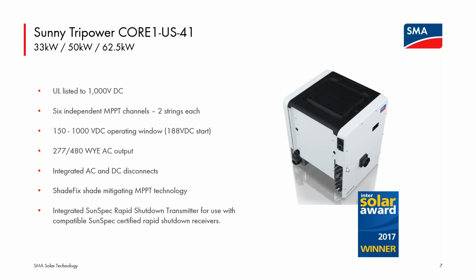The DC inputs, we'll talk about these connectors. These are Amphenol UTX connectors here at the bulkhead of the inverter. We include in the accessories bag shipped with each and every inverter the mating Amphenol UTX connectors and ferrules to crimp on the inverter end of the home run cables coming from the array. So installers will be able to mate Amphenol UTX to Amphenol UTX at the inverter bulkhead. And we provide sealing caps for any unused inputs. You can load the inverter unequally. You don't have to use all of the inputs, but you should be attaching something to each and every one of those plugs during installation, be it a home run cable or a sealing cap.